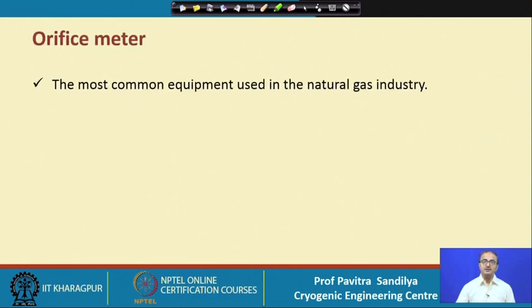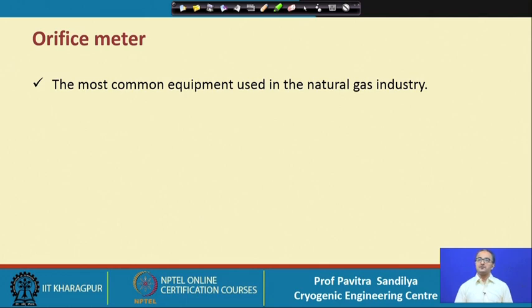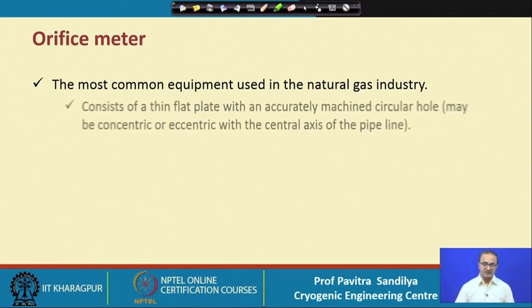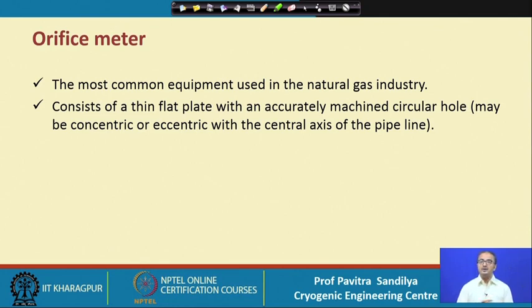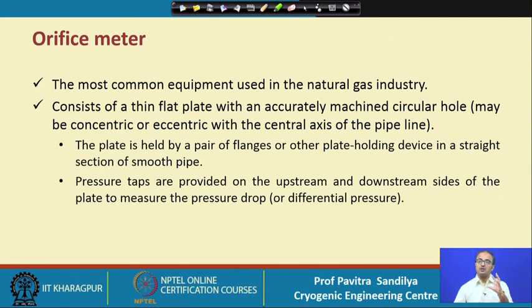Coming to the orifice meter — it is the most commonly used flow meter in industry because of its simplicity of operation, simplicity of design, and ease of installation. The orifice meter consists of a thin plate, machined properly, with a concentric hole — meaning it is a circular plate with a concentric hole generally.